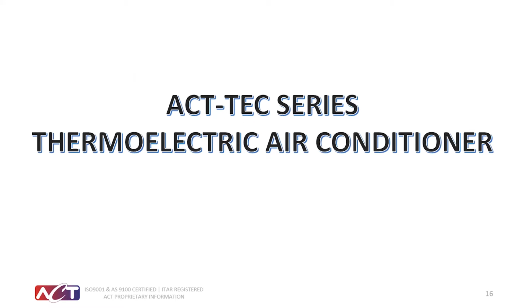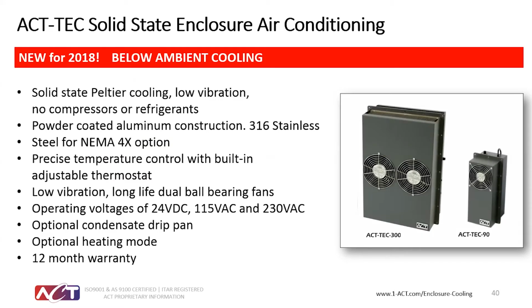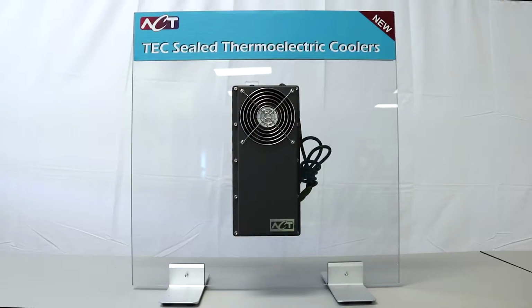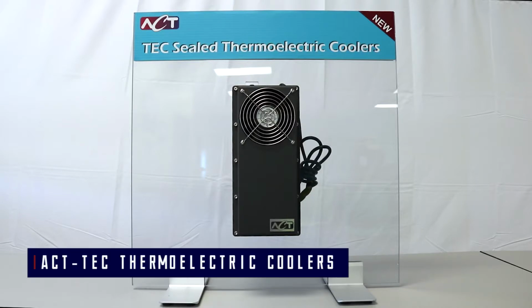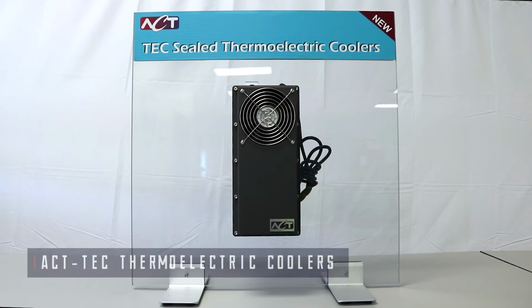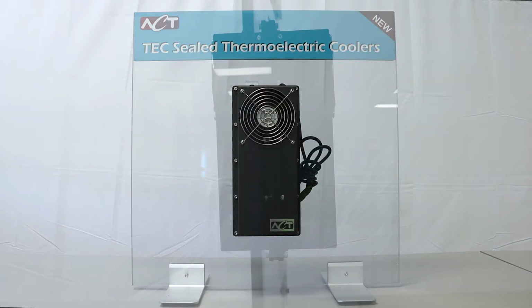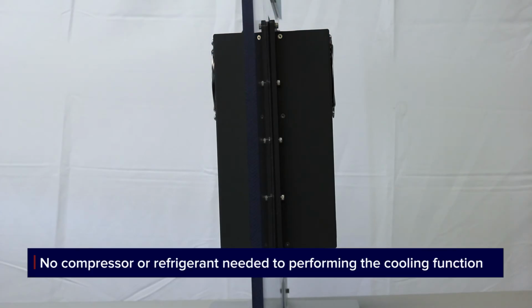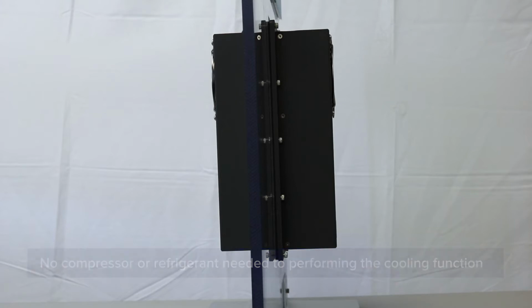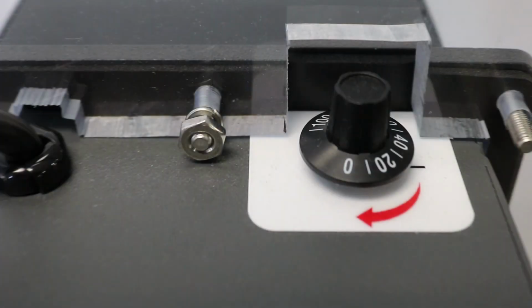ACT TECs are available to address internal enclosure heat loads of 90 watts or 300 BTUs per hour, and 300 watts or 1000 BTUs per hour. Our thermoelectric cooler incorporates Peltier electronics to convert the incoming voltage to cool the enclosure. A major advantage is that there is no compressor or refrigerant needed to perform the cooling function. Precise temperature control and internal cabinet humidity control are additional applied advantages.